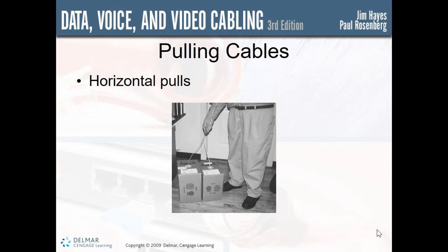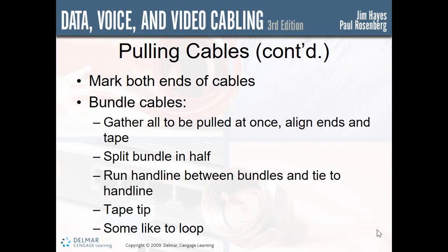Put caution tape around the ladder that you're working on and keep everyone away for safety, theirs as well as yours. And in the path you will be taking with the pull, carefully remove every other ceiling tile along the route, but leave them above the ceiling to prevent damage, because you don't want somebody bumping into them in the hallway and breaking them. After checking out the area and finding the most direct route, tie a weight to the hand line or a pull string, typically a nylon rope, and then starting at one end, toss it from end to end. So basically what we're doing here is we're going to start at one end, take a pull string, throw it all the way down from point A to point B, tie that to our cables, and then gently feed our wires. When we get to the other end, we want to mark both ends of our cable, so we know that cable 1 is going to the location of cable 1 in the closet.